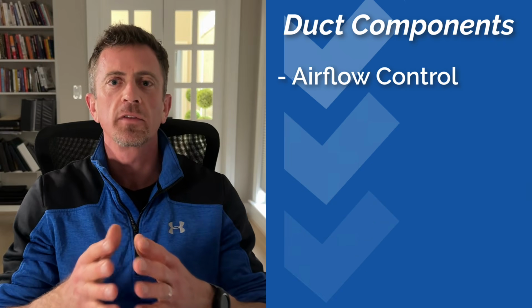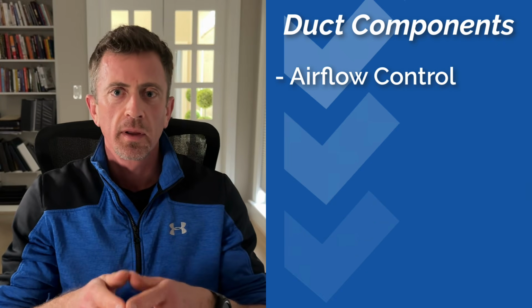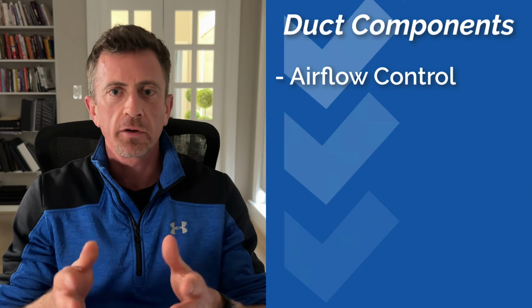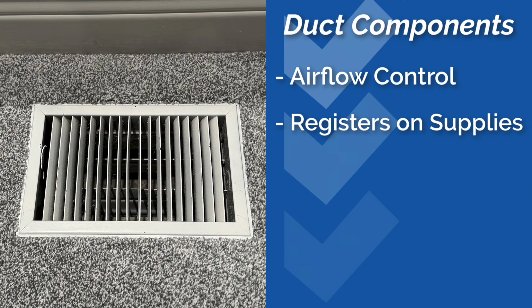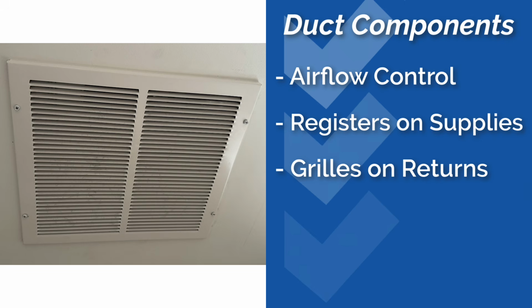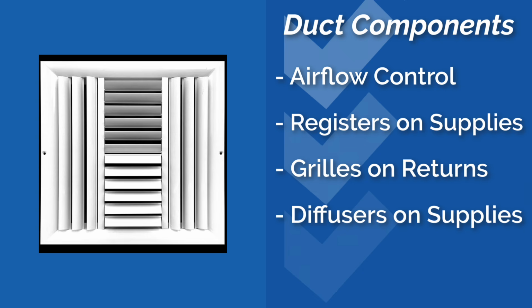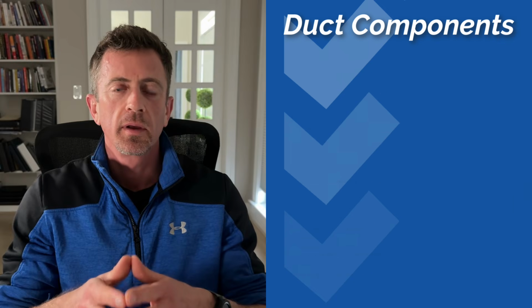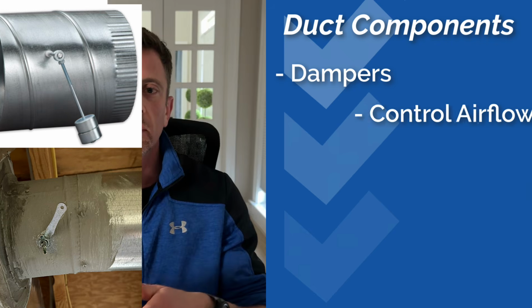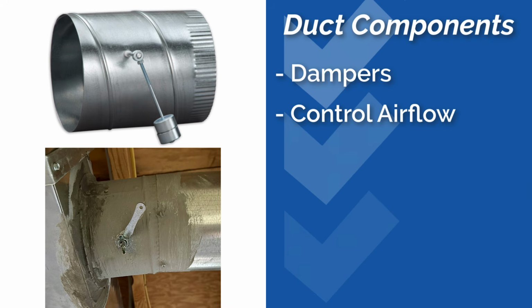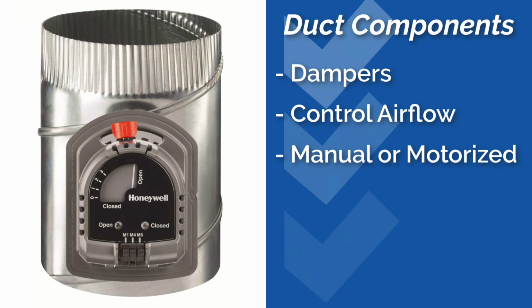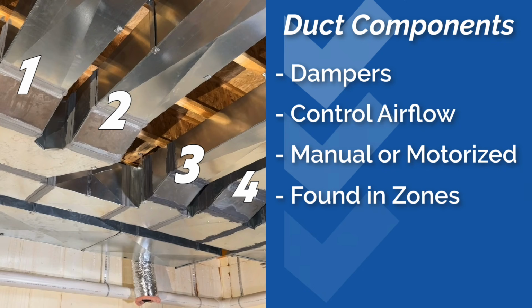Next, let's talk about airflow control and distribution. The vents that are attached to your ductwork are called registers if they are supplies, grills if they're returns, or diffusers sometimes. Changing these up can affect the way that the air gets distributed throughout a room and can actually improve performance if you choose the right type. Next up are dampers. Dampers control airflow in ducts, whether they're manual or motorized. Dampers are always found in zone systems as well.